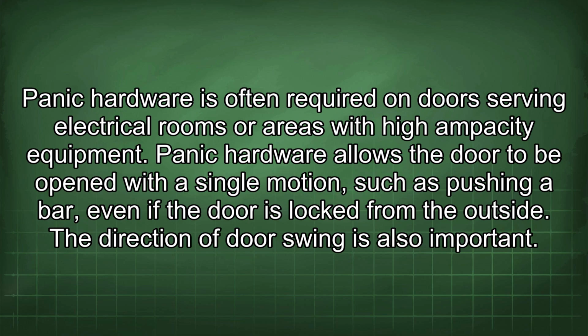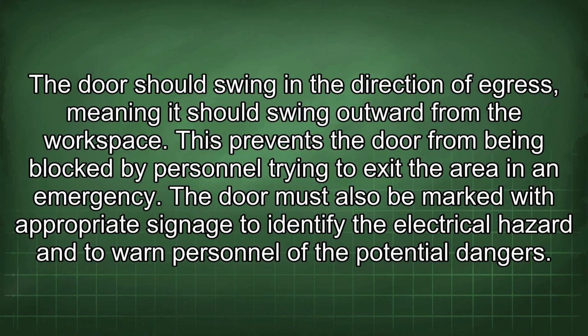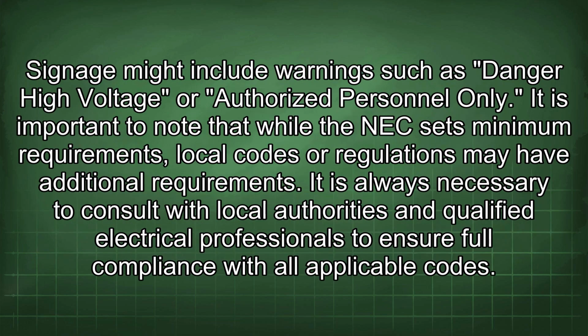The direction of door swing is also important. The door should swing in the direction of egress, meaning it should swing outward from the workspace. This prevents the door from being blocked by personnel trying to exit the area in an emergency. The door must also be marked with appropriate signage to identify the electrical hazard and to warn personnel of the potential dangers. Signage might include warnings such as danger high voltage or authorized personnel only.